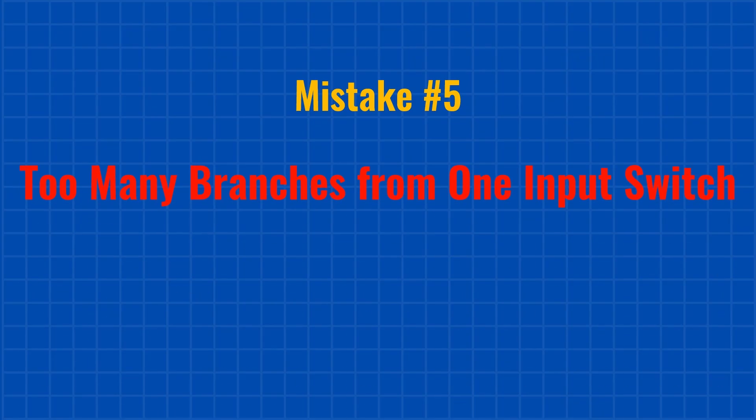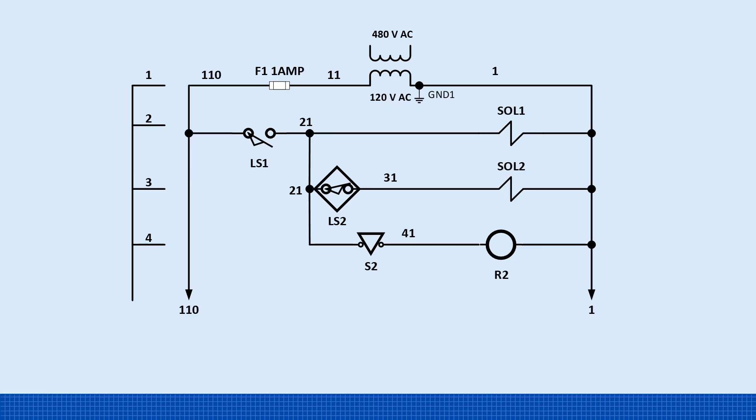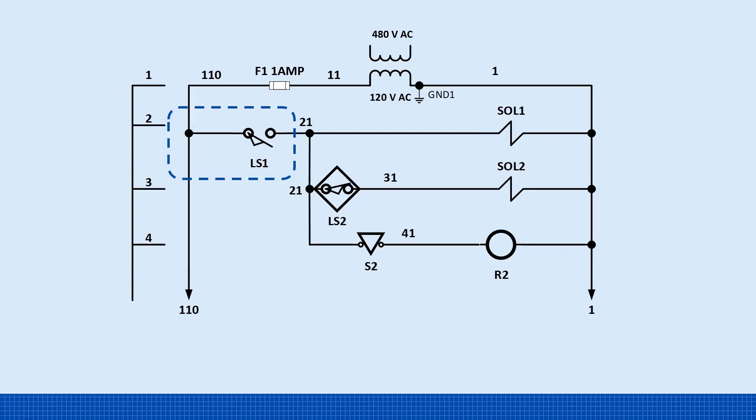Mistake number five. Too many branches from one input switch. Take a look at this schematic. The limit switch LS1 feeds three branches through wire 21, each controlling a load: solenoid 1, solenoid 2, and relay 2. The issue here is that all the current flows through LS1, including inrush currents from these inductive loads. LS1 is a mechanical switch, not designed for high combined current, and over time, this can damage its contacts. Also, running multiple branches from a single switch may work, but it's not good practice.